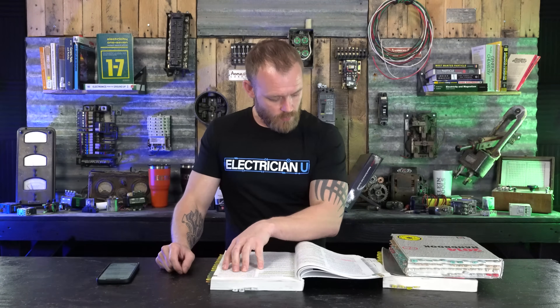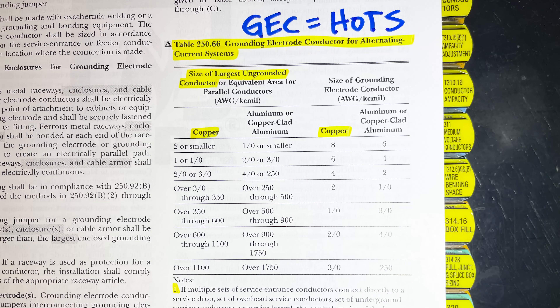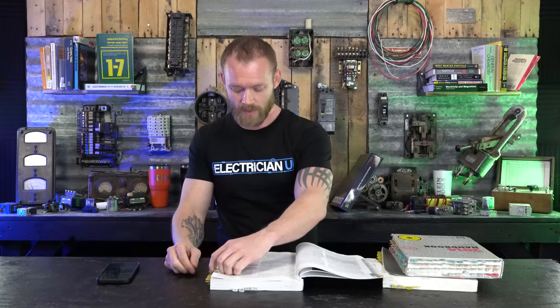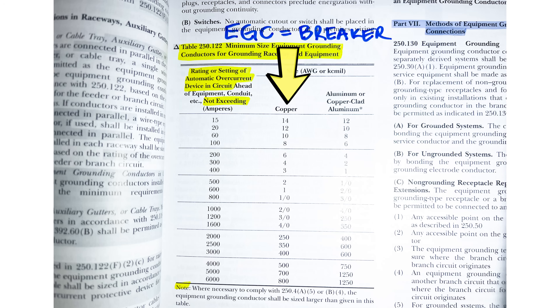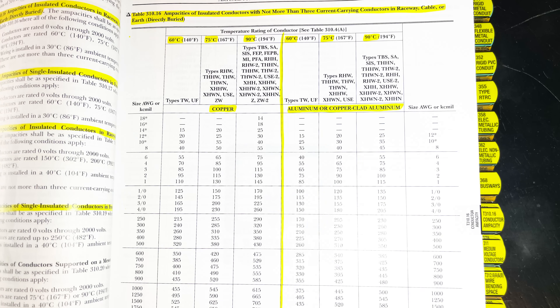Then I go to table 250.66 and highlight it. I used to highlight the entire copper column on both sides, but I've been doing this long enough that I know what that table contains. Next I go to table 250.122 and highlight the name — you could also highlight the entire left-hand column and the copper column to show what breaker sizes go with what conductor for equipment grounding conductors.